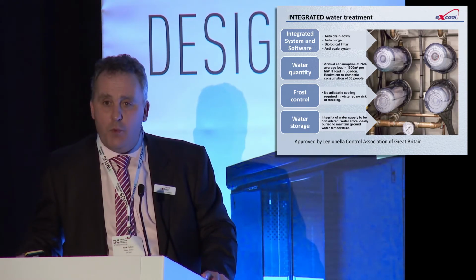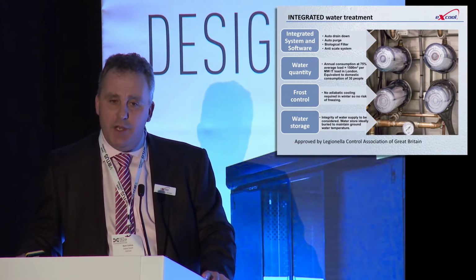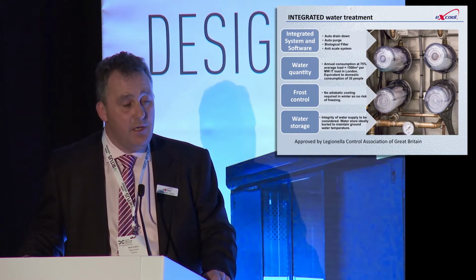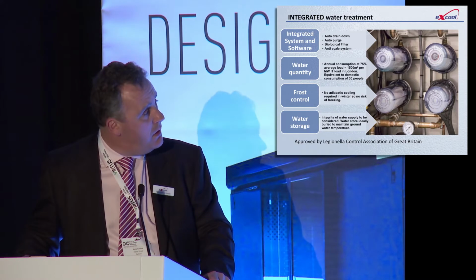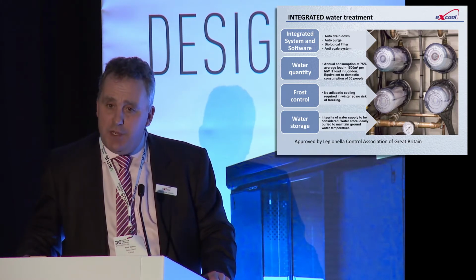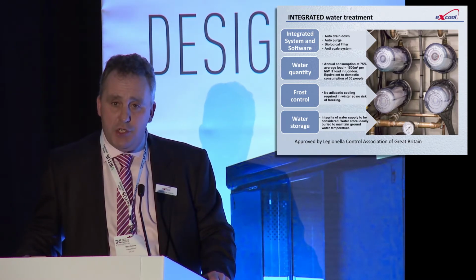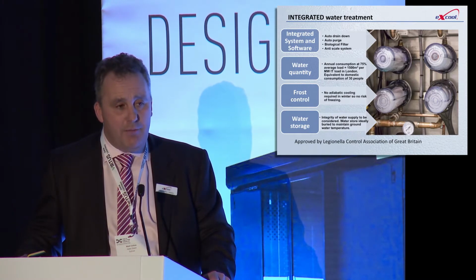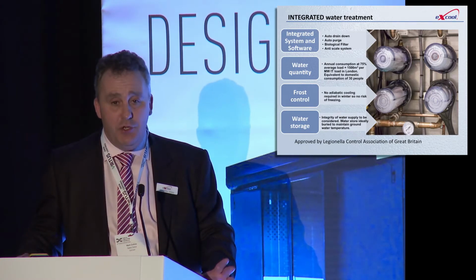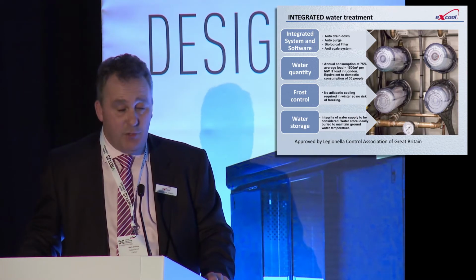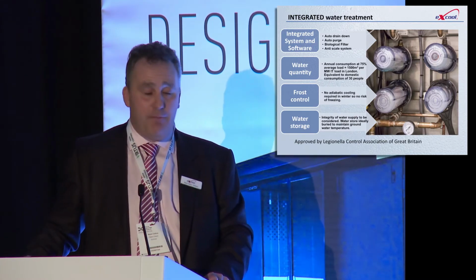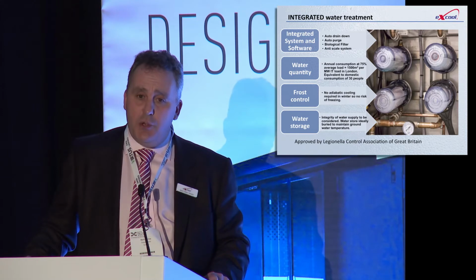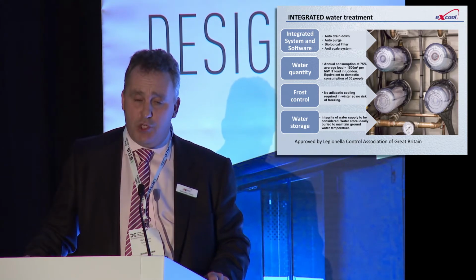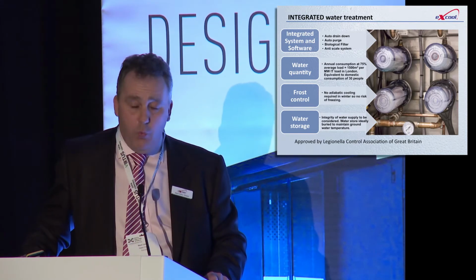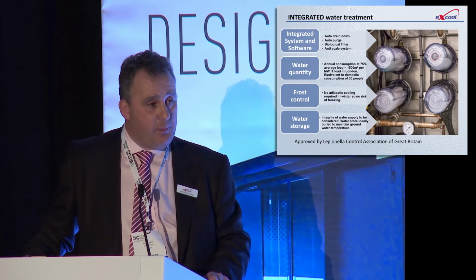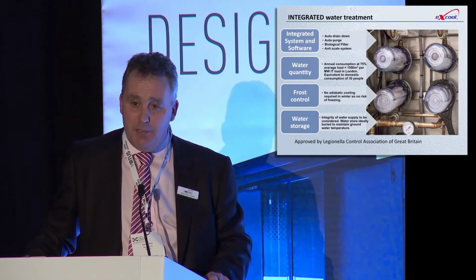Frost control, we don't need to worry about frost control in the middle of winter because we're not spraying water in the middle of winter. The system is dry. The one thing that does need to be considered here is water storage. In areas where you may have two completely separate water supplies, you don't need to worry about water storage. That's a real luxury, and there aren't many places in the world that have that. So we need to consider burying or storing and keeping cool a store of water, because if we lose the water supply, then quite clearly we lose the cooling ability in the middle of summer.